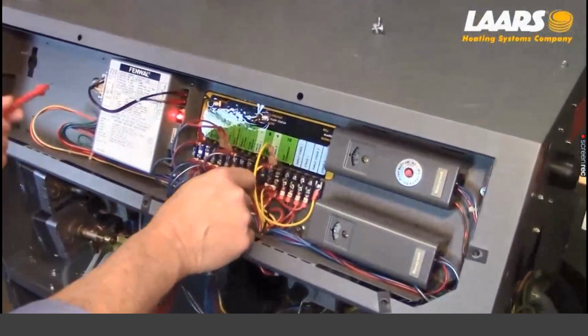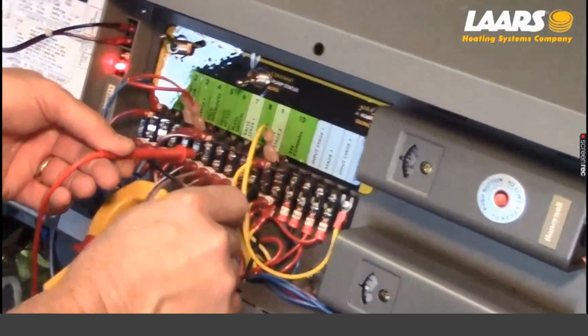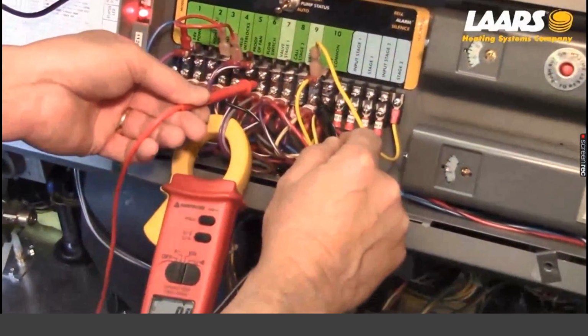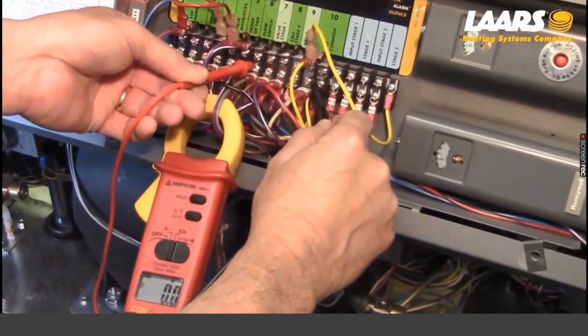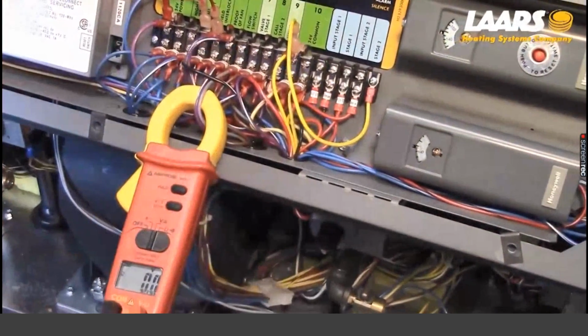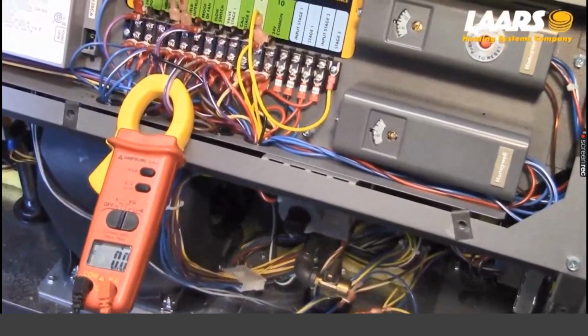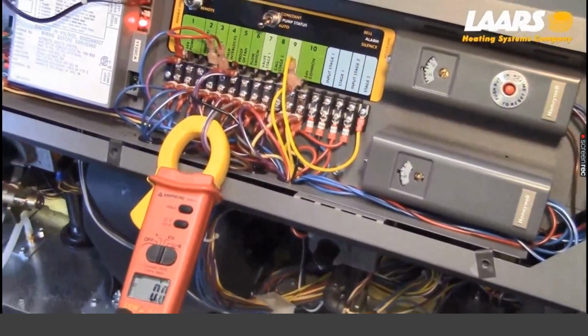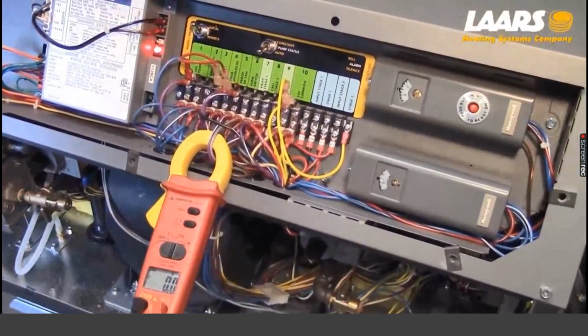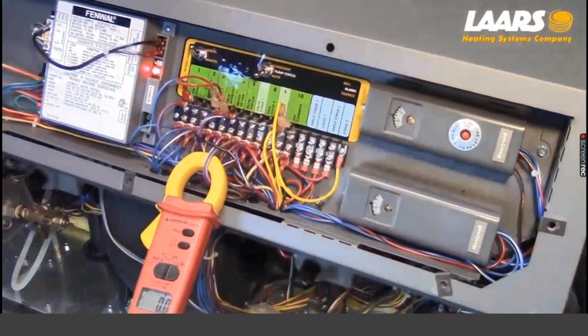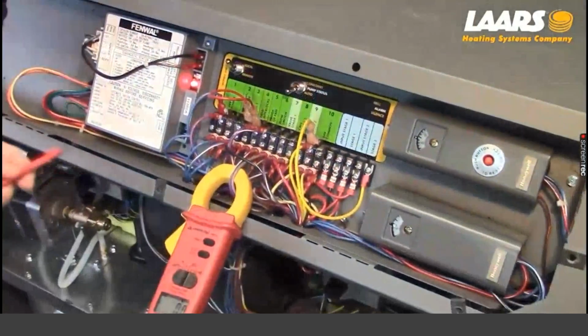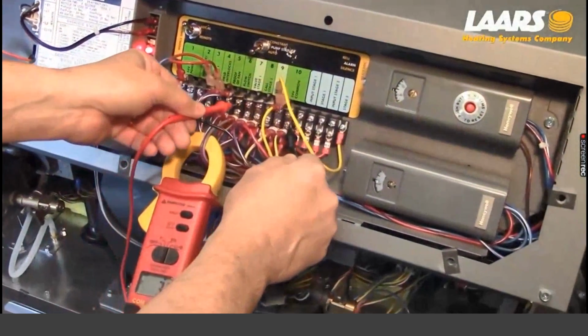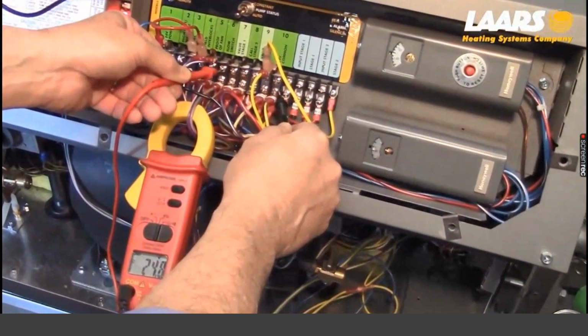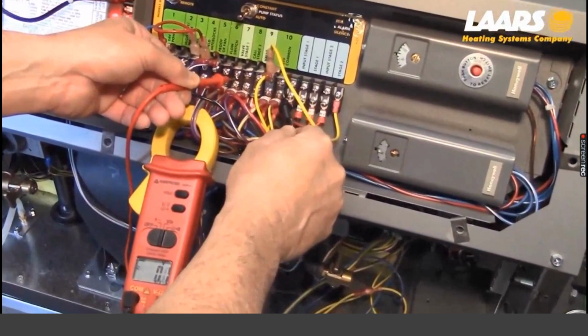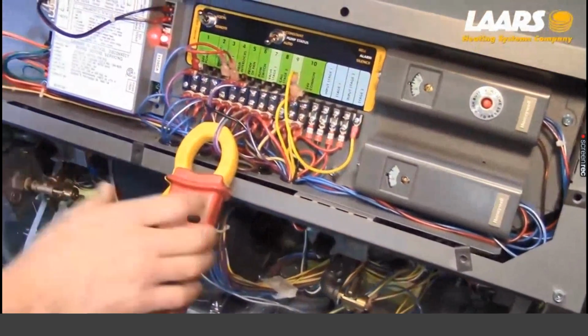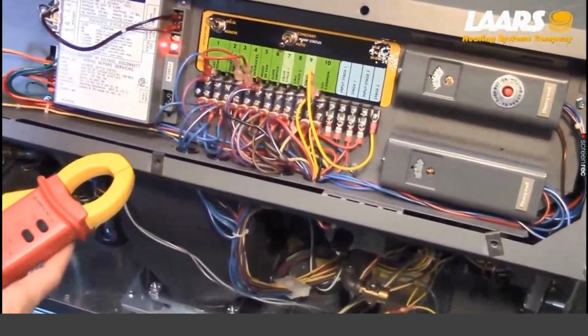Next, we're going to walk across. The boiler still doesn't fire, so I have it here at proof of fan, but I do not have it at my flow switch. All right, that means something's going on with the pump, the coupling, the flow switch paddle. Double check to make sure your pump is running, etc. All right, in this example, I left our pump off, so I'm going to power up our pump. So now, I have my flow switch made, which now I'm going to start going in for a call for heat, okay?